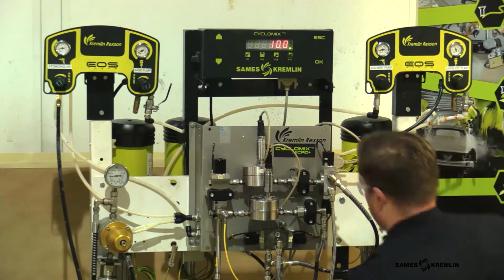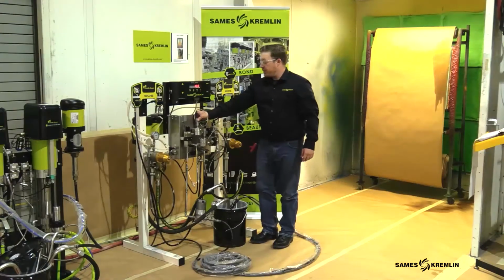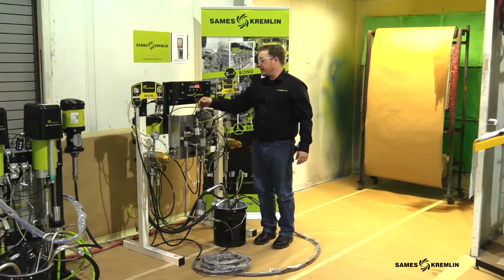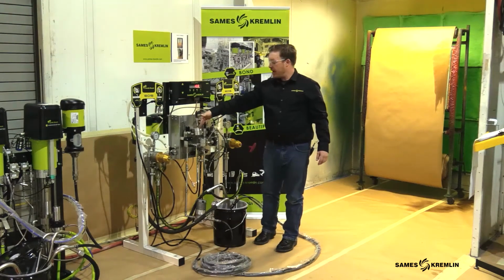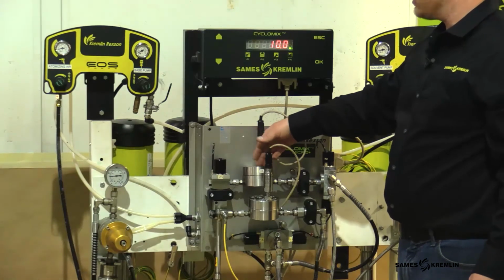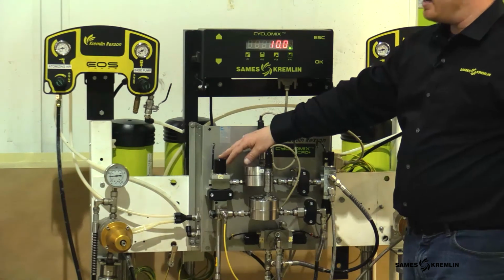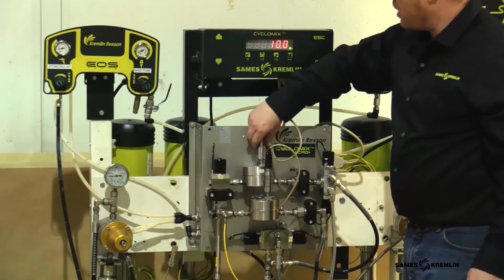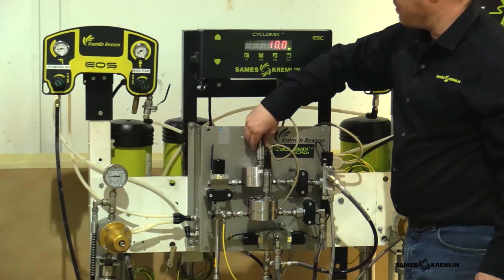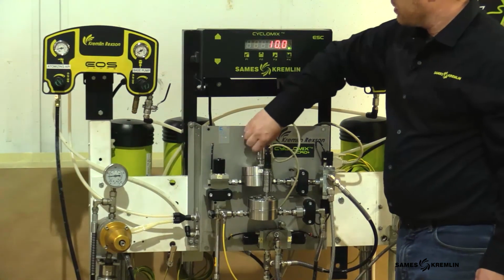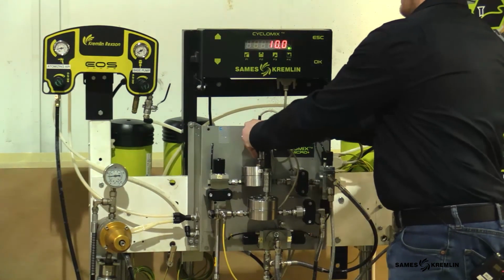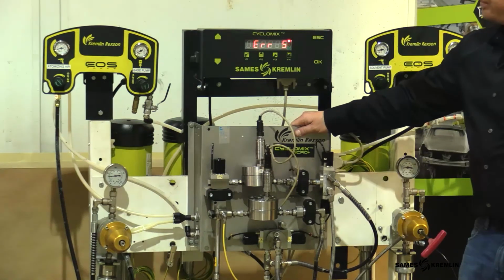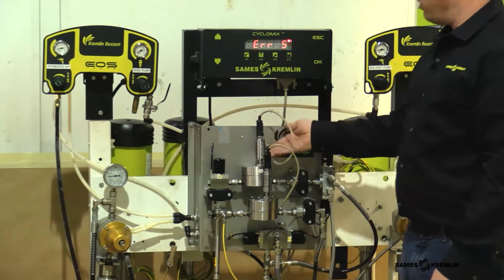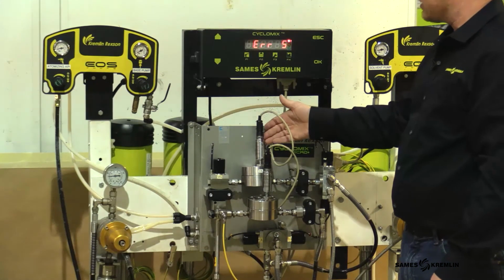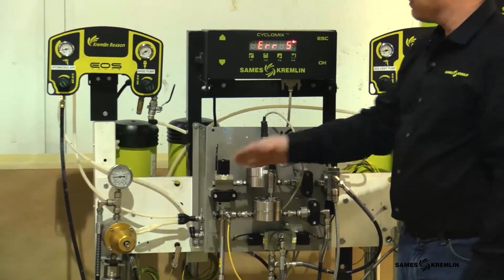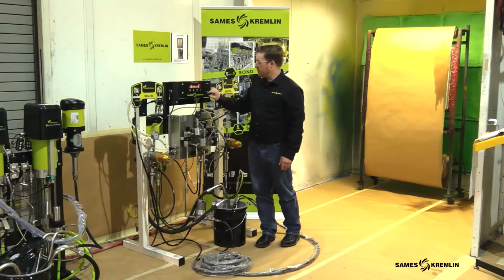So then one other error that I can produce for you is going to be the error 5. And like I said, error 5 is going to be where the catalyst flow meter is picking up pulses when the VP6 valve is not energized. So I will pulse this simply by moving these back and forth. Error 5. So error 5, we saw pulses and counts on the catalyst side when we shouldn't have. Faulted us out.